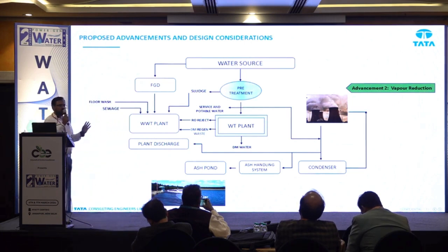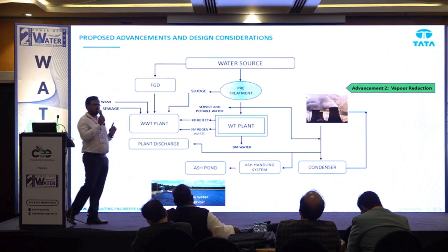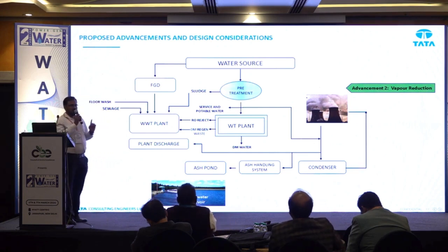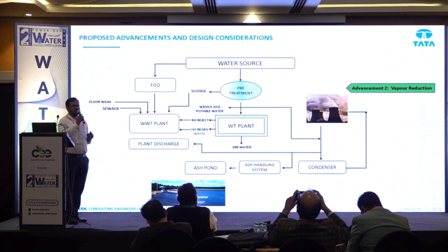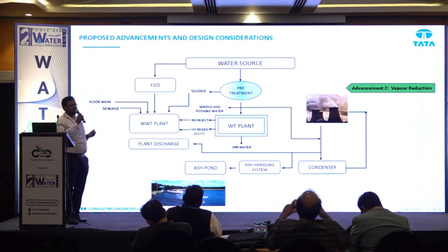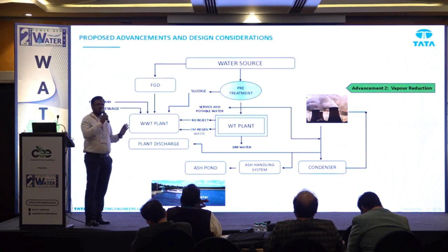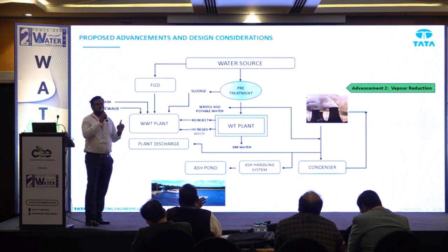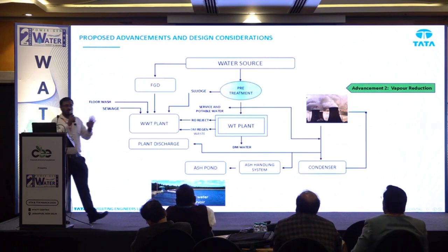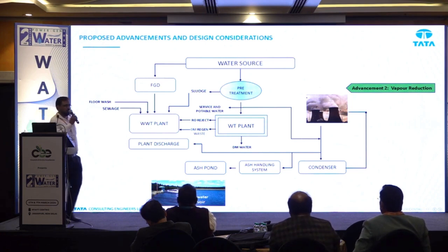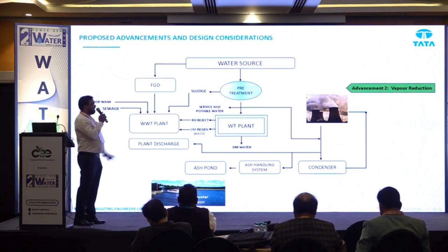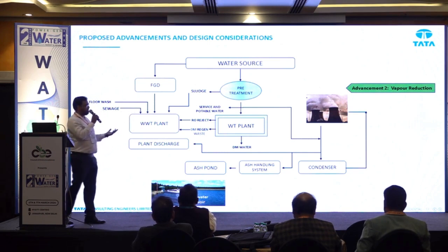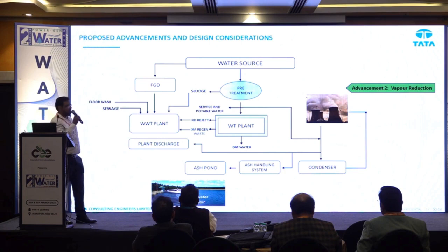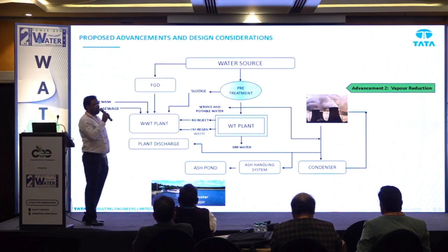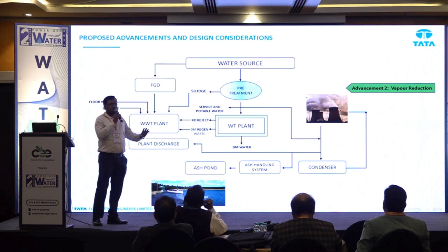This is the second advancement. The second advancement is vapor reduction, where the evaporation loss is almost 1.5% to 1.7%. In 2 into 800 megawatt, at 1.5%, where the cooling tower capacity is 8400 meter cube, your evaporation loss for 1 into 800 megawatt will come to around 1400 meter cube. So a huge quantity of water, as I explained, is lost to the atmosphere through evaporation.